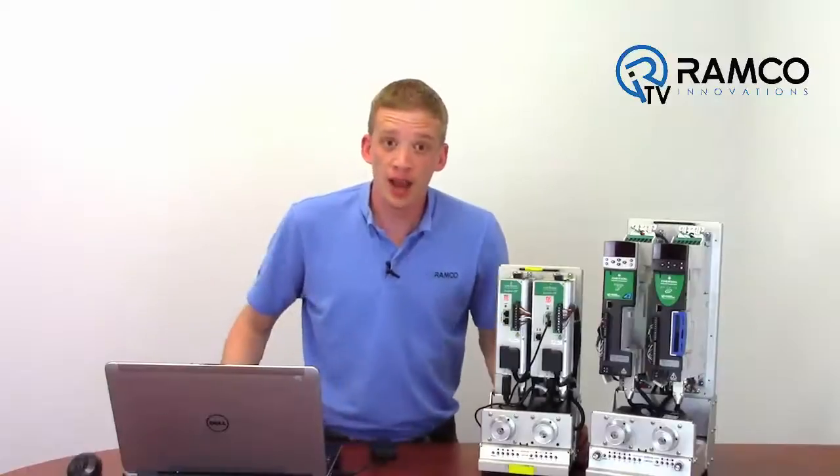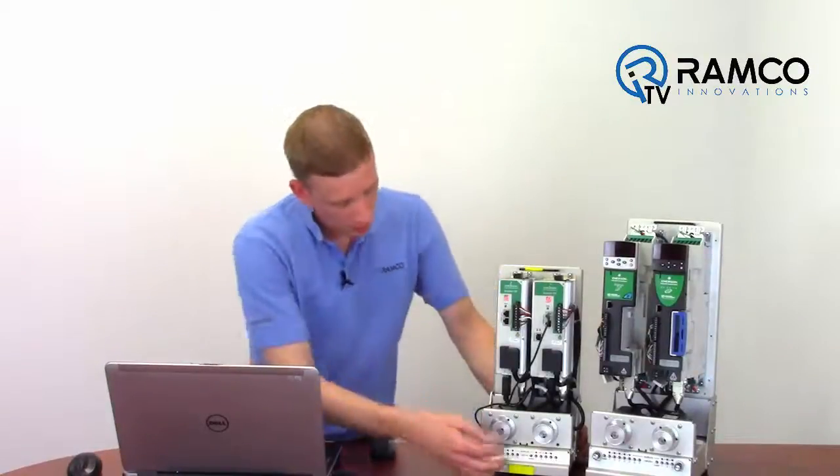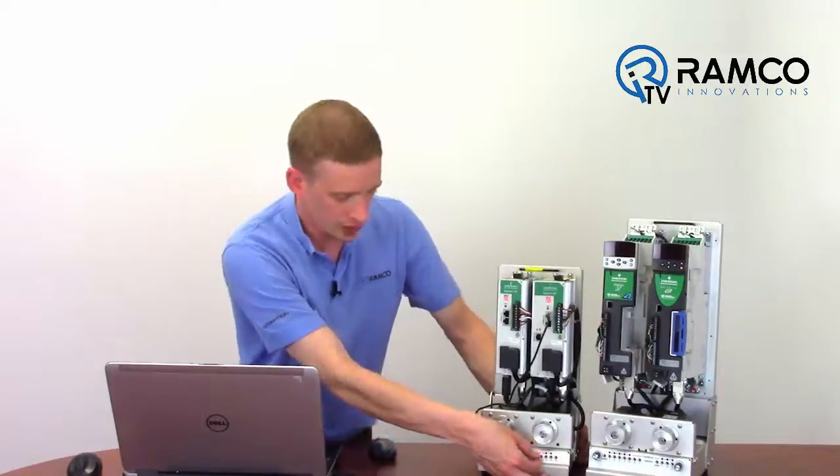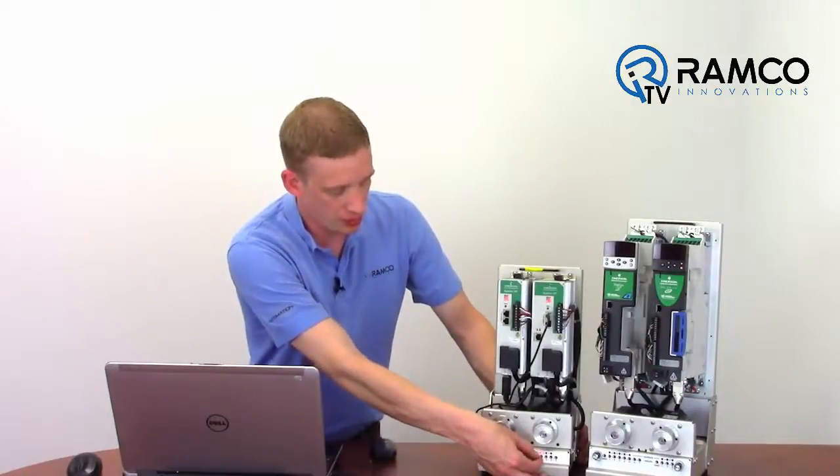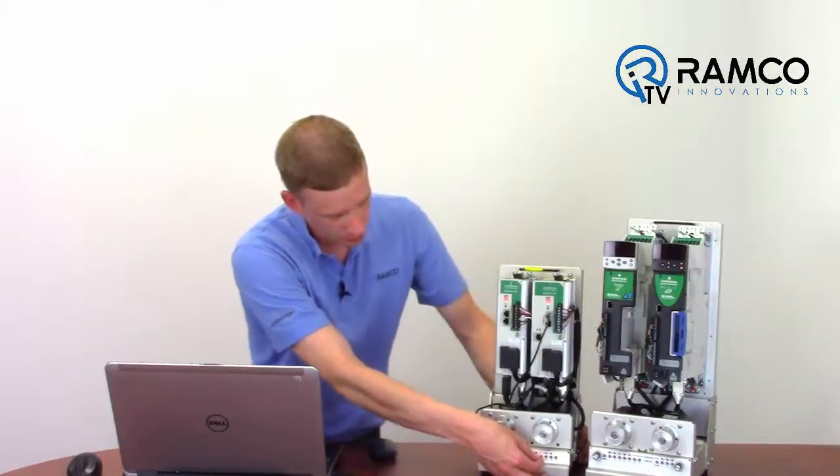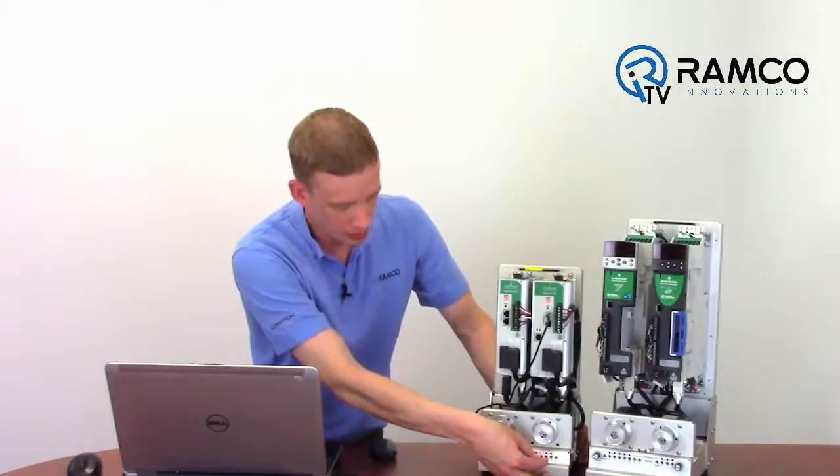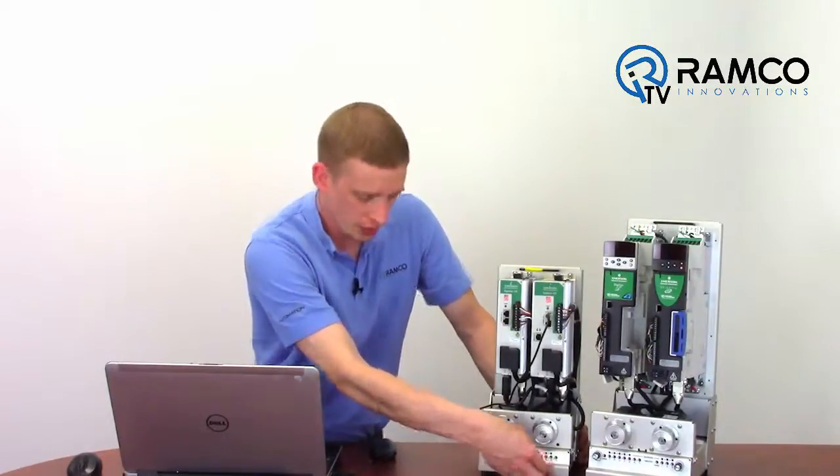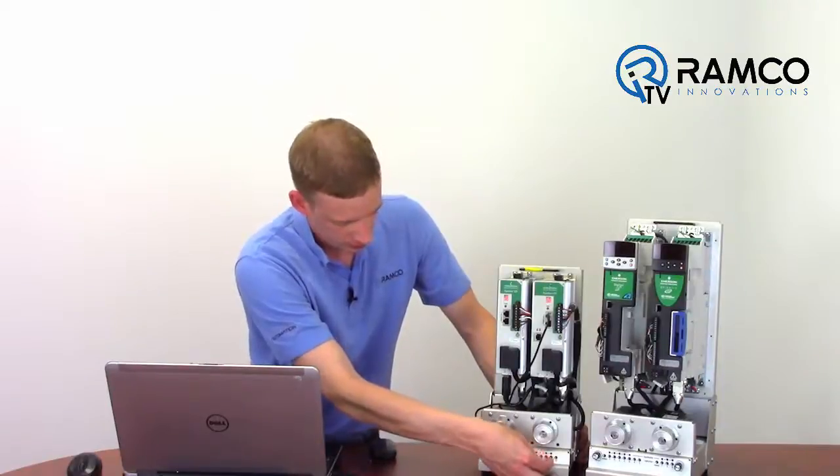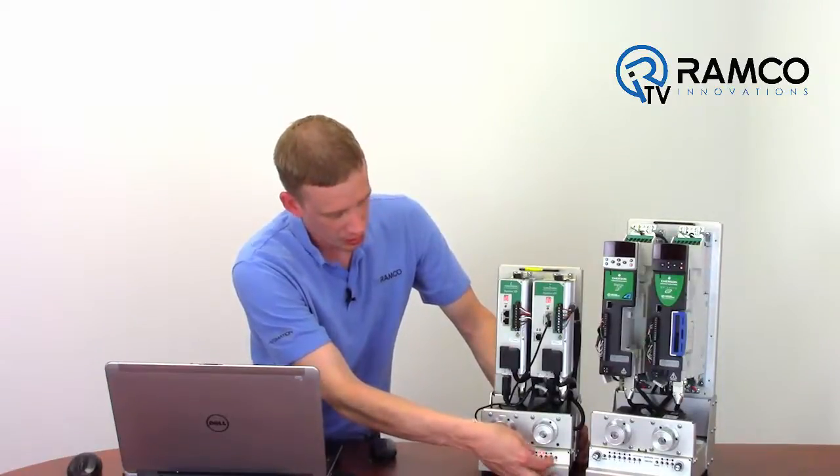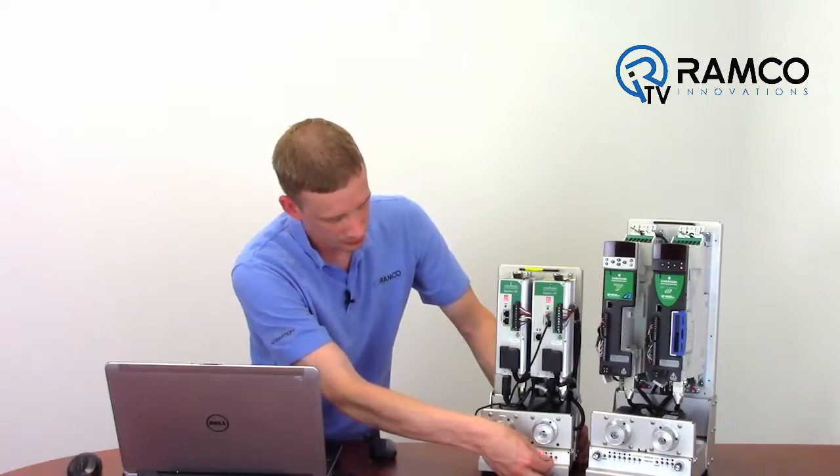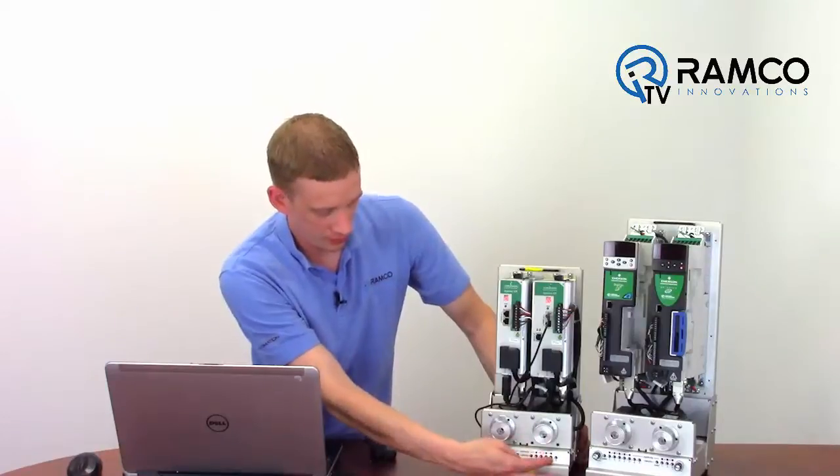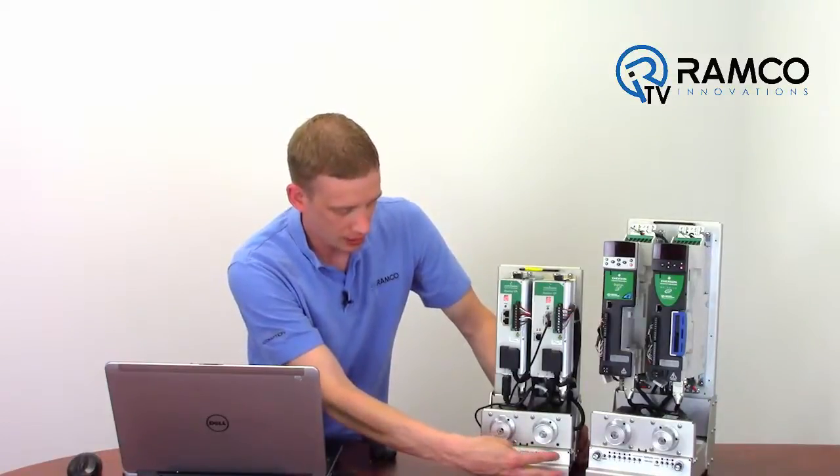Okay, now that the drive is programmed let's see if this works. First thing I'm going to do is try and jog, hit the first input that I've programmed. Going in forward direction and reverse. Okay, a homing sequence. Simulate the prox switch. Back to the marker and now finally an index.